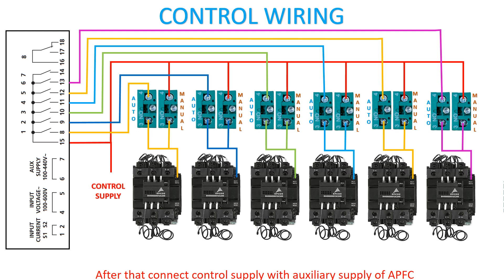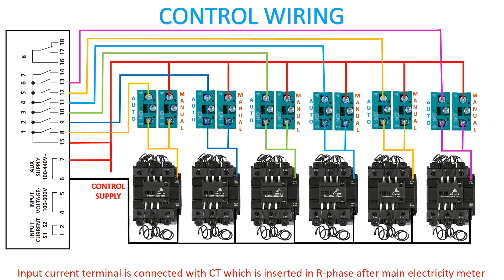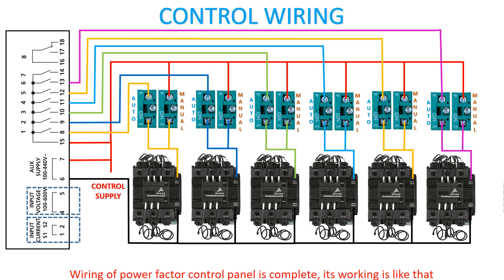After that, connect control supply with the auxiliary supply of APFC. Always check the auxiliary supply of any electrical equipment carefully. Finally, connect neutral with the other terminal of the contactor coil. The input current terminal is connected with CT, which is inserted in the phase after the main electricity meter. The input voltage terminal is connected with Y and B phase. Wiring of the power factor control panel is complete.